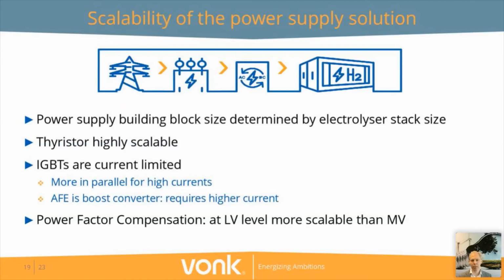For power factor compensation, I already mentioned that having it at low voltage level is an advantage when it comes to scalability. The main driver for this is that you can integrate it within your power supply building block, which means if you want to scale to a larger scale power supply for a larger scale electrolysis facility, you just add more building blocks. However, if you apply power factor compensation at medium voltage level, for each project size and different circumstances regarding the local grid, you need to recalculate, re-engineer, and remanufacture your medium voltage power factor compensation.